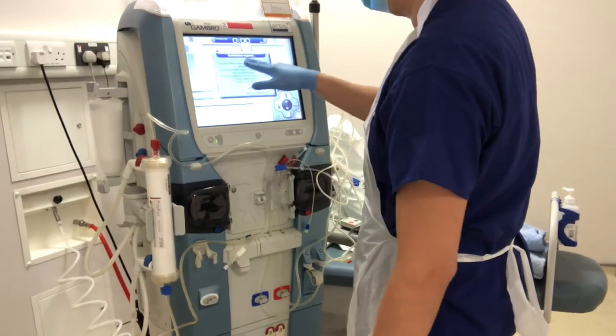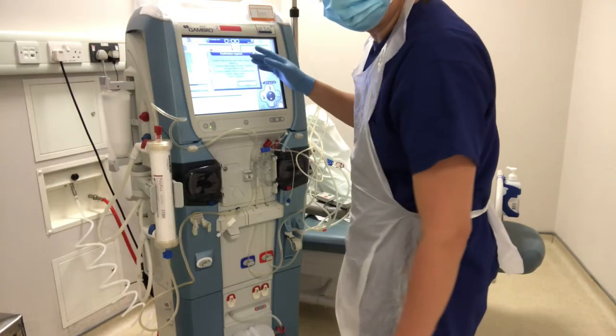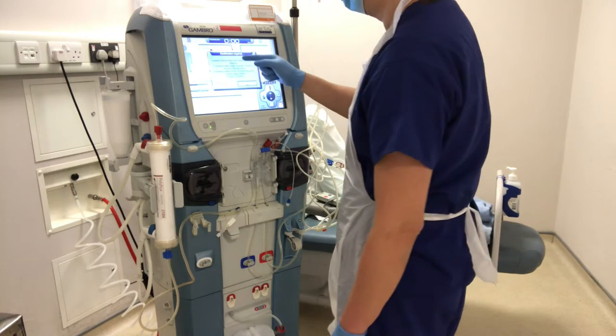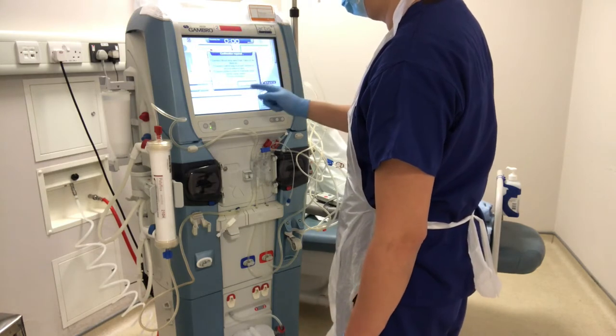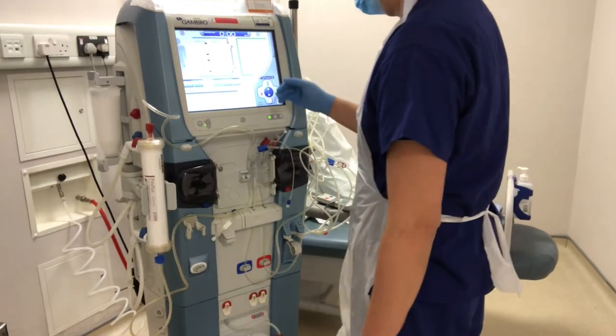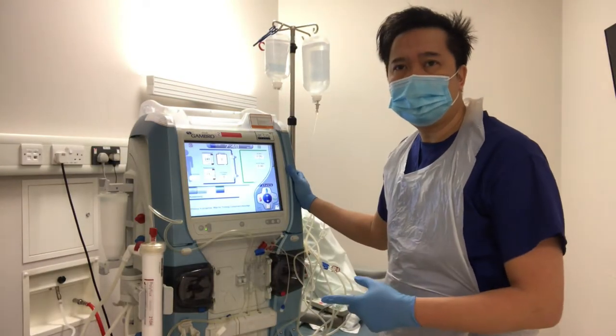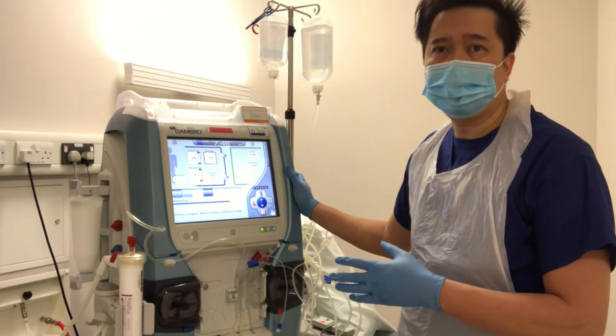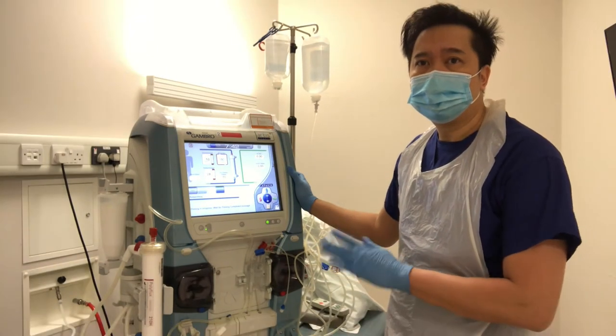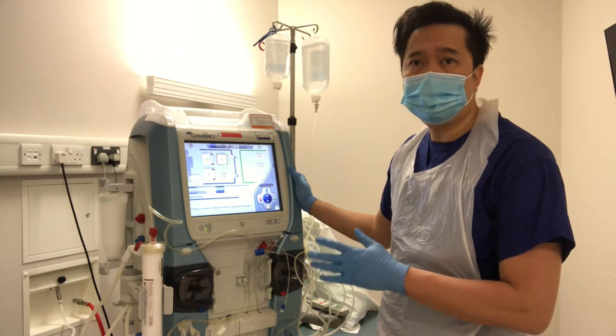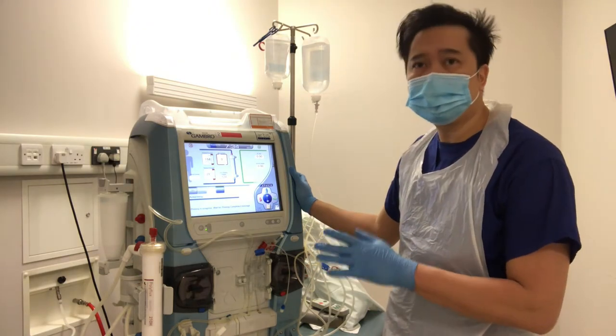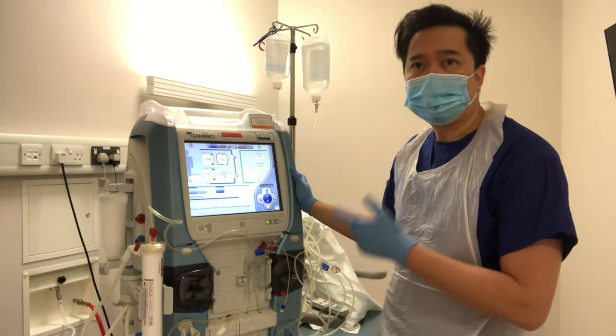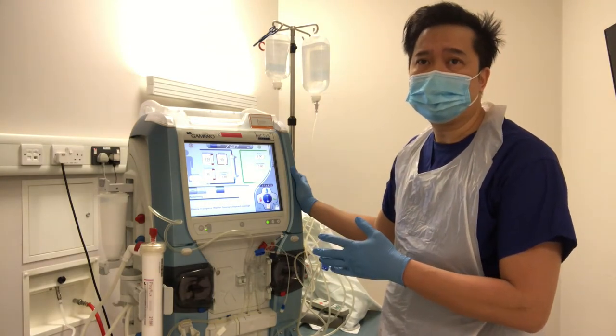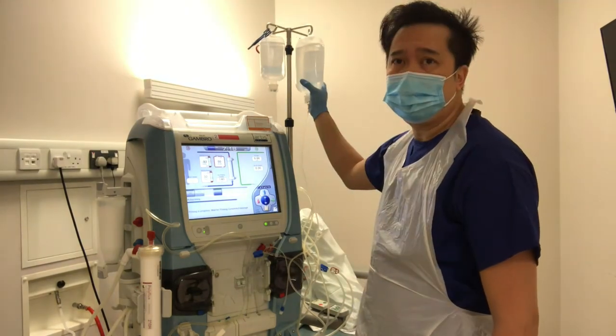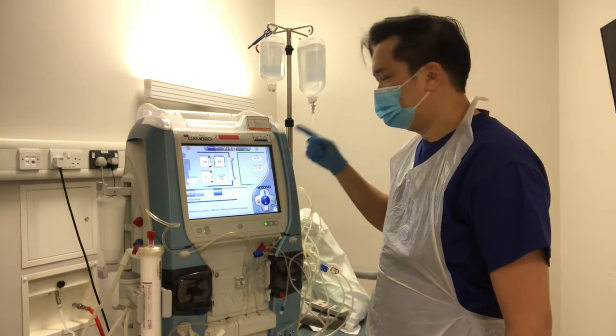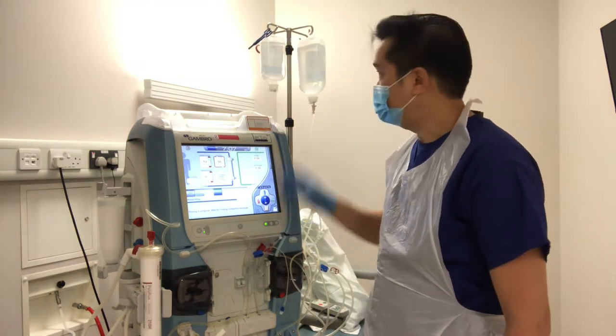So, there's a confirmation required for the machine for us to start the priming process. So, it's all here written. So, you just have to confirm if you already done that. So that will prime automatically. So here we're going to do an ordinary intermittent hemodialysis. So some hemodialysis machines do the HDF. So we're not going to do the HDF for today. Instead, we're going to do the intermittent hemodialysis. So as you can see, we're just using ordinary normal saline, 1 liter. And the machine will try to prime the bloodline with this saline.